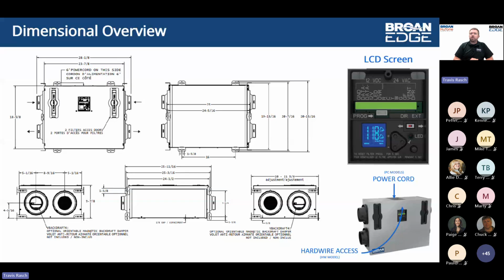Down below that connector block, you see that LCD screen interface. So in this case, we're seeing the 110 CFM on both the supply and the exhaust side, as well as to the right of that screen, you have your buttons you're going to push to fully commission the product, make any changes you would need to the configuration of the product. And then finally, you can see just above to the right of those buttons, that red switch, and that's for our in-field selectable airflow configuration, again, which I'll cover a little bit here shortly. And then just below that, you see that LED indicator light. So that will illuminate if there's any maintenance or filter maintenance required.